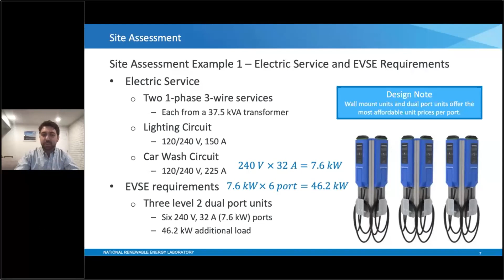However, we did notice that this was quite a bit of electricity that we'll be consuming, and looking at both of those circuits, they were actually already quite full and quite at capacity. So what we needed to do was consider expanding one of the service panels. What we did was we're expanding one of the services to actually a 400 amp service panel that will then separately feed the 150 amp lighting load we have here on the top right. Then we'll also be installing a separate service panel that will be servicing these new 3 dual port EVSE units.